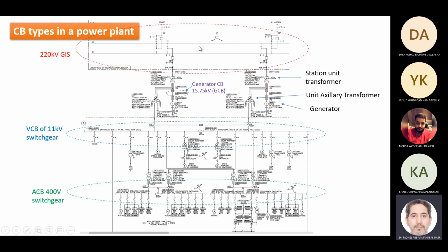To show you a single line diagram from one of the power plants, this is a real single line diagram from a plant. We have the single line showing two generators connected to a double bus, and these are the transmission lines. This breaker connects to a transmission line. Each generator here is connected to a delta star transformer, delta at the generator side, star at the HV side.